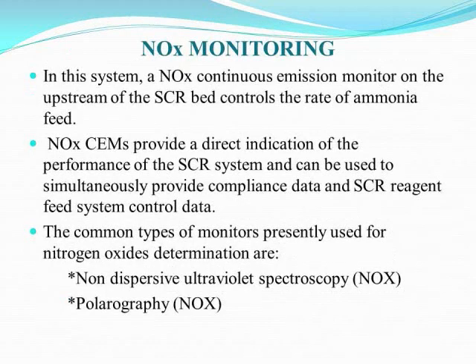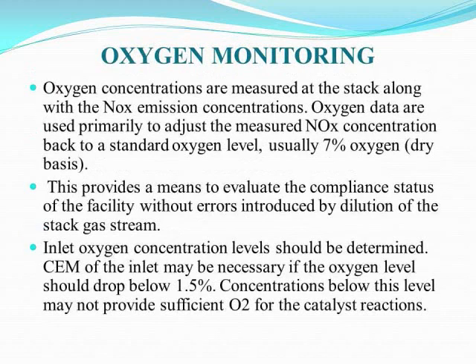Ammonia injection can be controlled by an automatic shutoff valve. A high ammonia-to-air ratio or low flue gas flow rate triggers the shutoff valve to close. The goal is to inject adequate ammonia into the reactor to remove NOx; however, if too much ammonia is injected, it will pass unreacted through the reactor and result in ammonia slip.